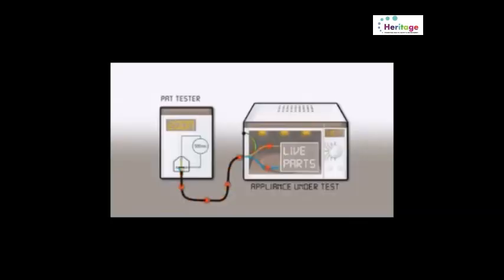Insulation testing is carried out by plugging the tested appliance into the PAT and applying a test voltage of 500 volts DC to both the live and neutral terminals of the mains plug. If the insulation is in good condition, a high insulation resistance reading is obtained, typically in the order of hundreds of megaohms. If there is a breakdown in insulation between live parts and protective earth, a current will flow across the insulation and back to the PAT via the protective earth conductor. The measured insulation resistance is greatly reduced, indicative of an insulation fault.